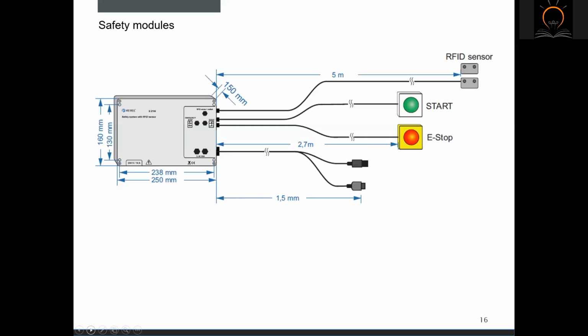We will see that all of the safety modules have more or less the same elements, starting with the main supply connector. So all safety modules have to be mains powered for operating. The second one is the coded RFID sensor. This sensor is installed into a Metrel test cage, but can also be installed into any third-party test cages.